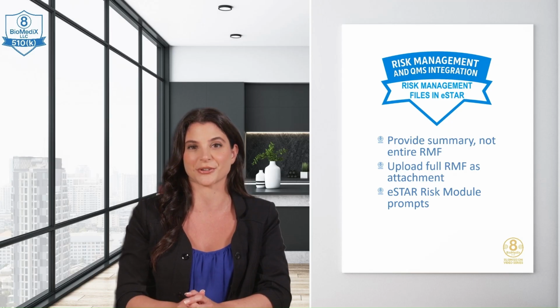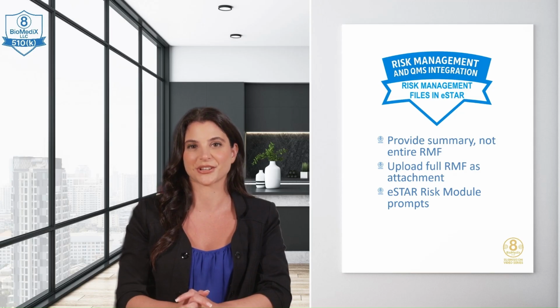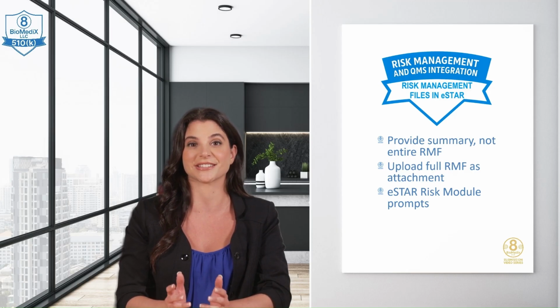Risk management files for eSTAR. Your complete risk management file, RMF, is a living document that captures all these activities. For your eSTAR submission, you generally won't input the entire RMF directly into eSTAR, but rather provide a comprehensive summary and upload the full, detailed RMF as an attachment. eSTAR has a dedicated risk management module.